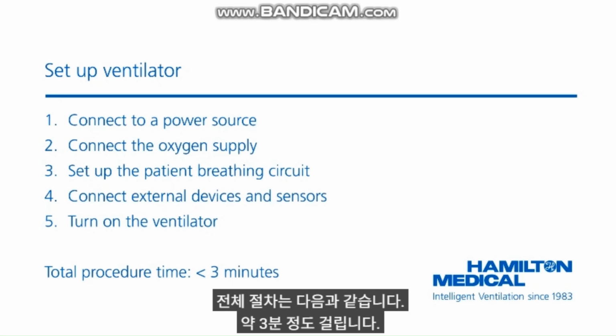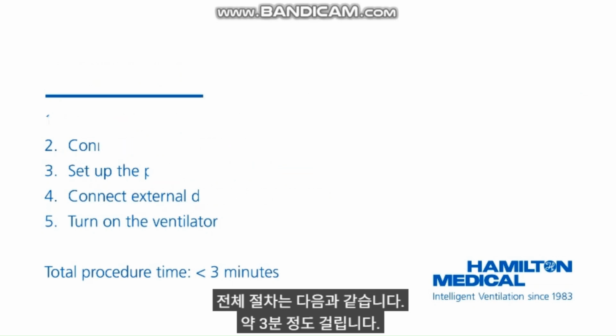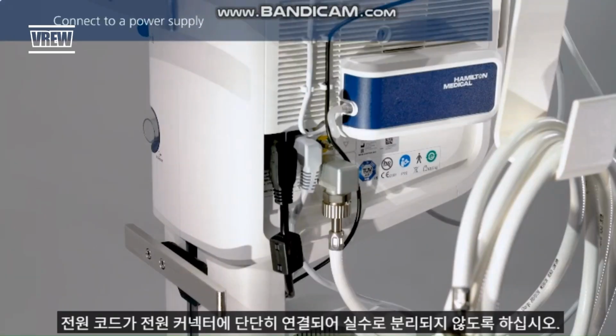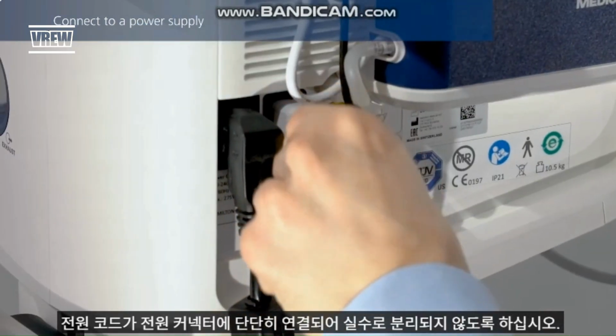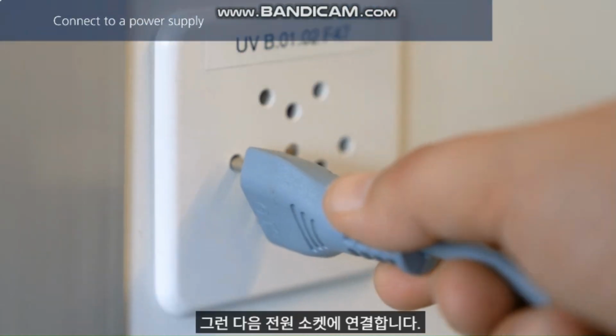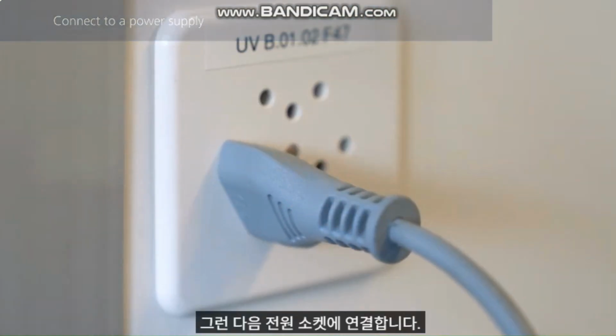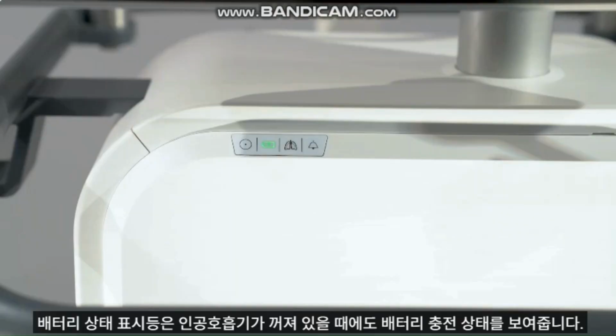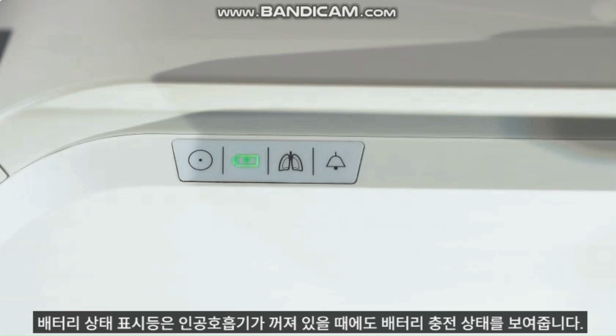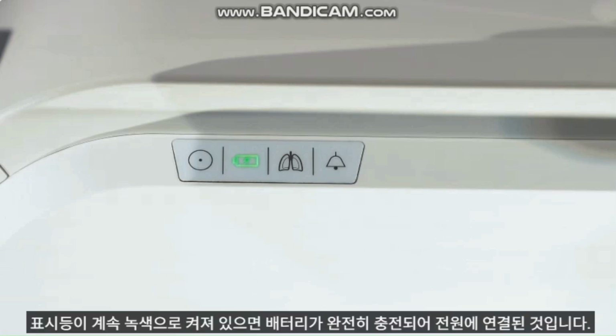The procedure takes approximately 3 minutes. Make sure the power cable is firmly connected in the socket to prevent accidental disconnection, and then connect it to the primary power outlet. The battery status indicator shows the charge status of the battery, even when the ventilator is turned off. When the indicator is solid green, the battery is fully charged and connected to primary power.